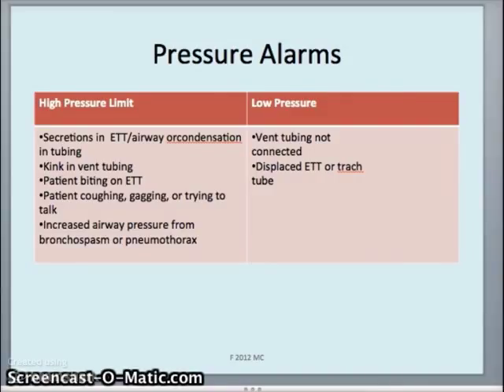So clearly, if you're going to hear a high pressure alarm and then call the respiratory therapist, and all that needs to be done is your patient needs to be suctioned, then they're not going to come running too much when you call, all right? So the first thing you're going to do is look at it, see if you can troubleshoot it. You go through these things and say, okay, is there a kink in the tubing? Is the patient trying to talk to me or coughing or biting on the tube? Maybe they need to be suctioned, okay? And then you investigate whether or not there's a more complicated thing like the airway pressure from a bronchospasm or pneumothorax. Low pressure alarms mean that something's not connected.